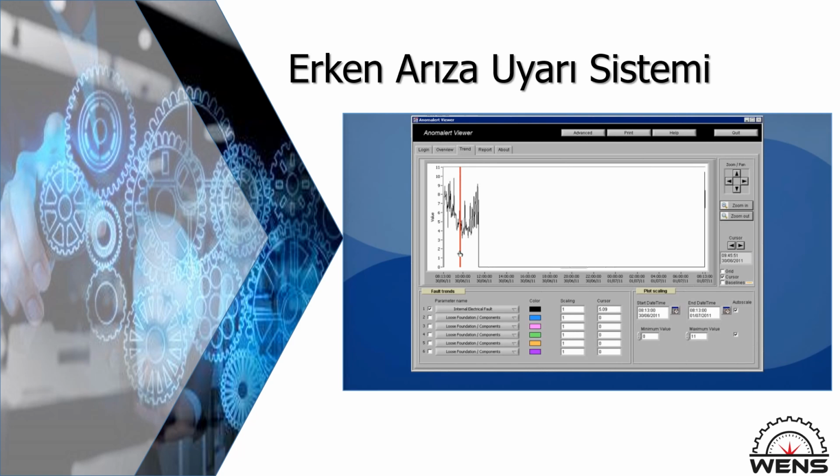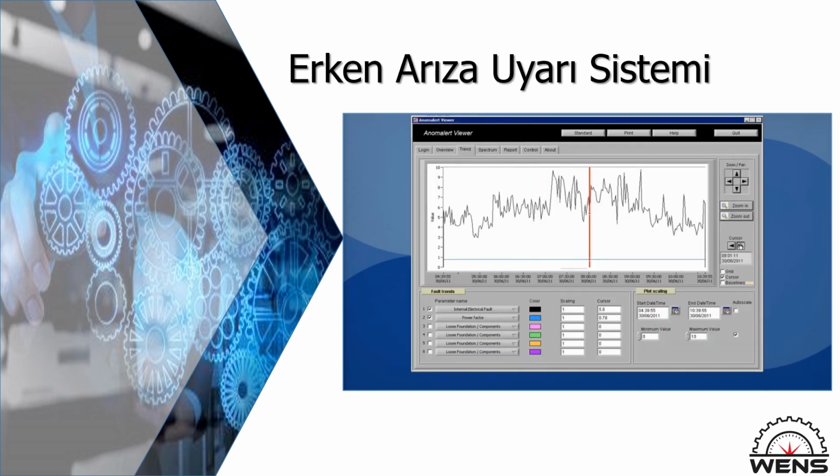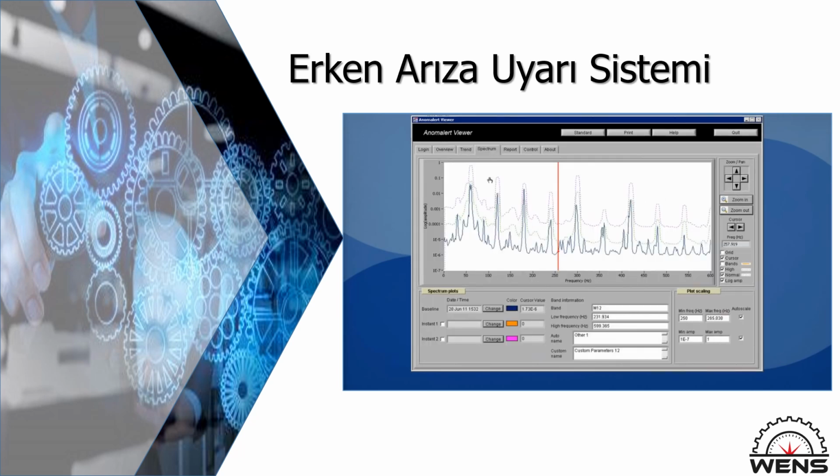Anom Alert first learns the equipment it's monitoring. After that, it provides information about the equipment's current condition. This includes automatically identifying any weak points in the equipment. Pressing the PSD button displays the equipment's frequency spectrum. Any abnormal peaks in their frequency indicate weak points that may result in faults. Thanks to Anom Alert, maintenance personnel can easily locate the faulty device.